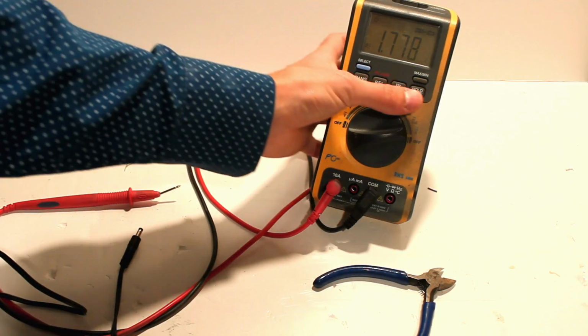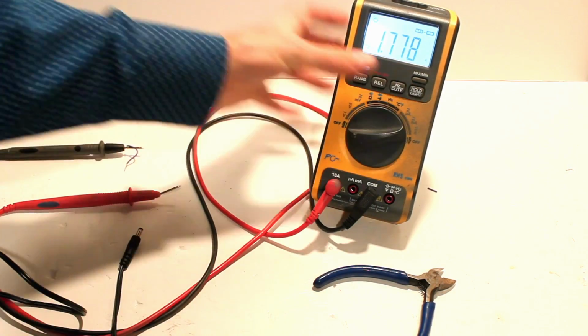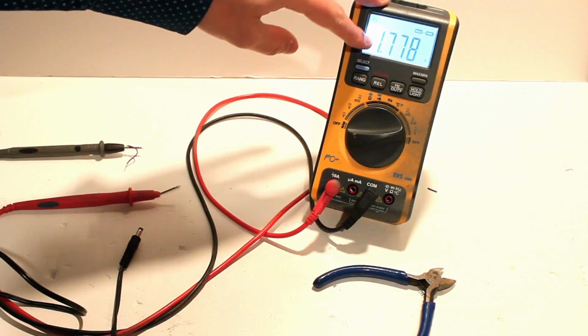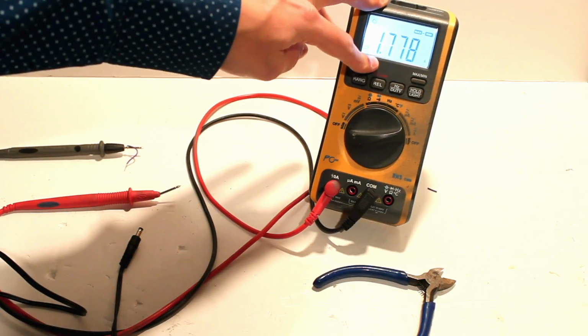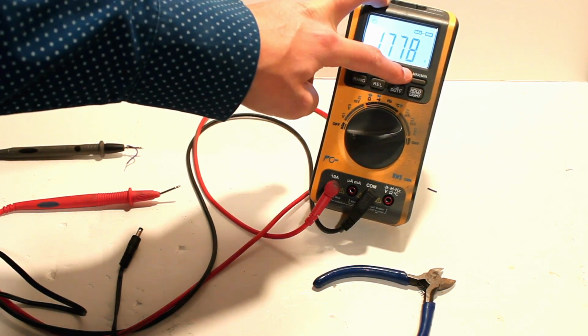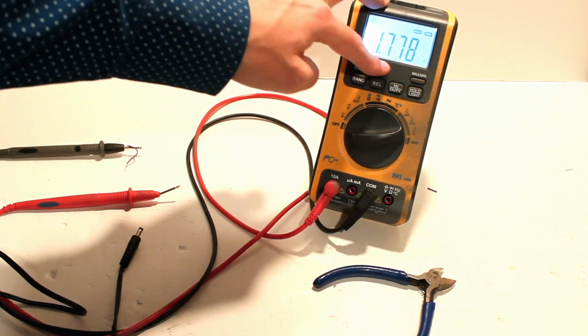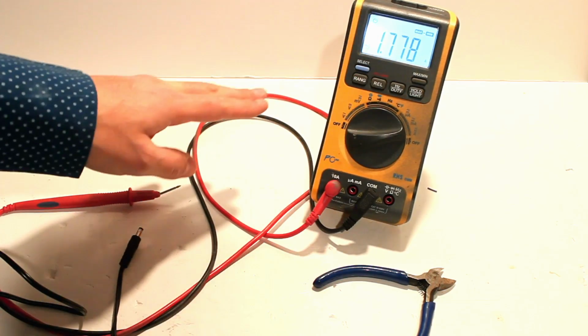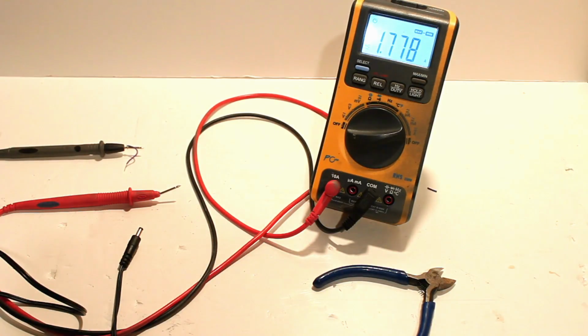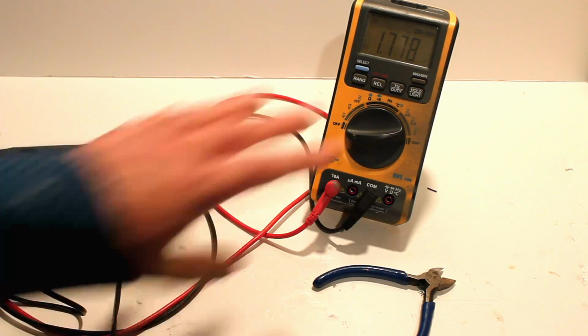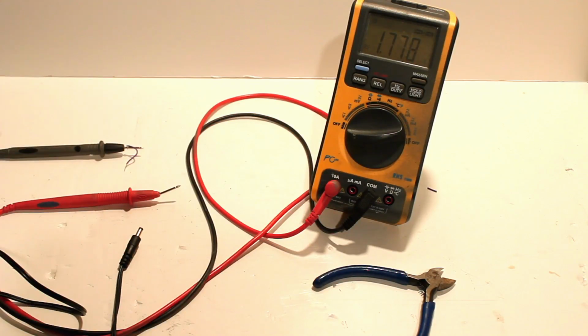What this shows me is the maximum peak reading of current it's got out of this wall supply is 1.778 amps. Now, I would only ever recommend doing this on a current limited supply, i.e. a power supply that transforms power down to a low current, low voltage, no more than 2 or 3 amps. Anything more than that, we risk overheating the multimeter, overheating the power supply, or possibly damaging it.